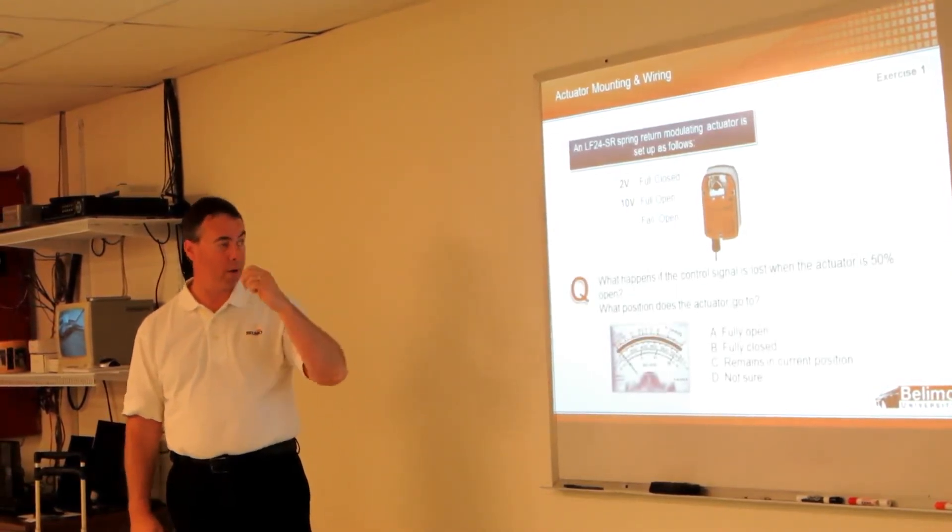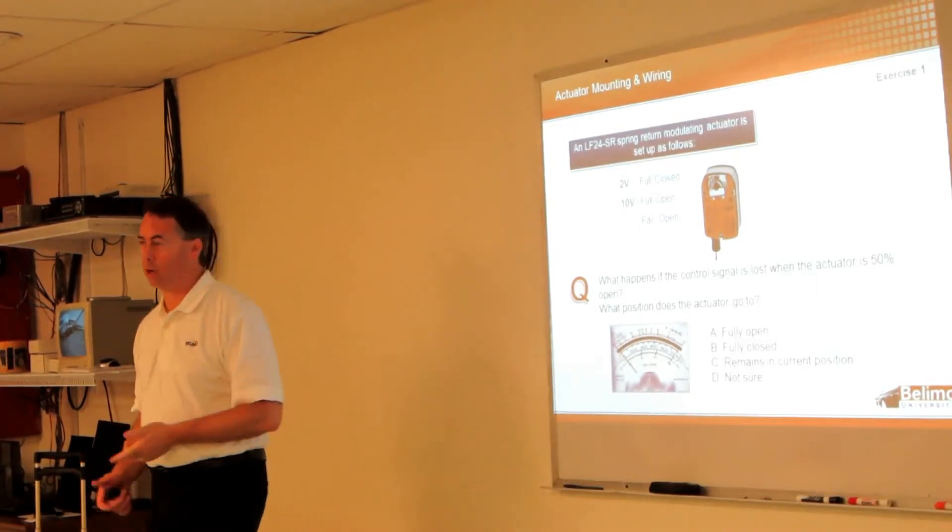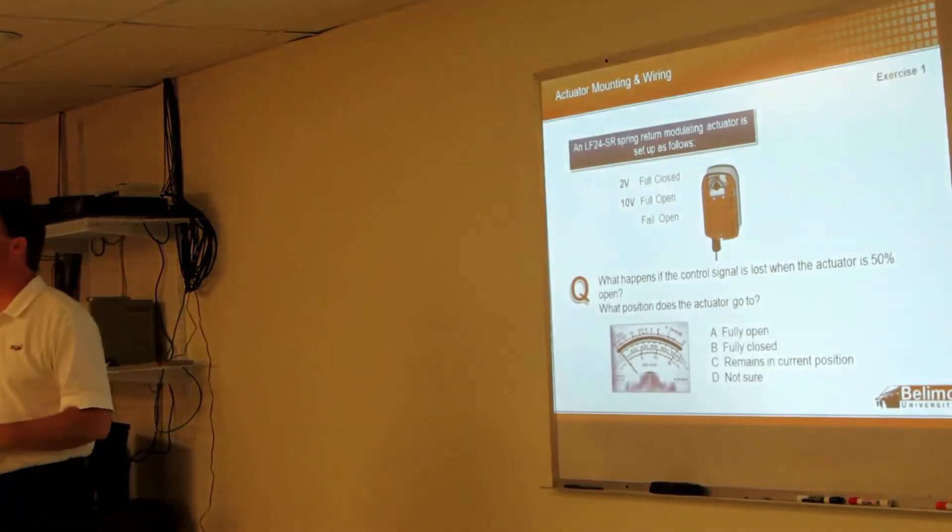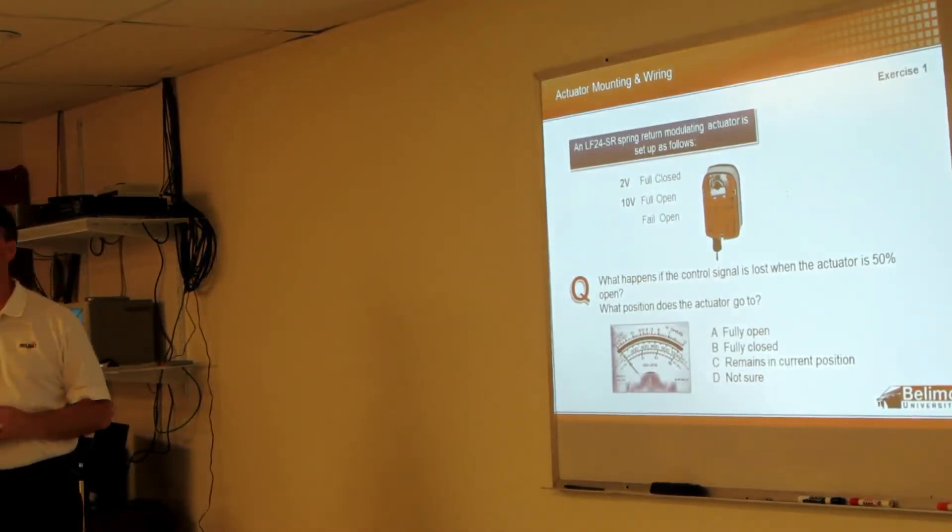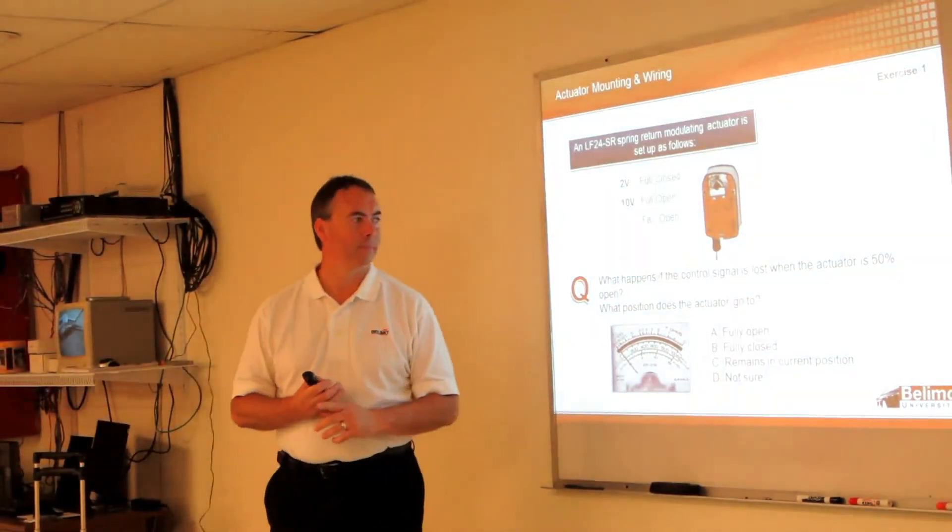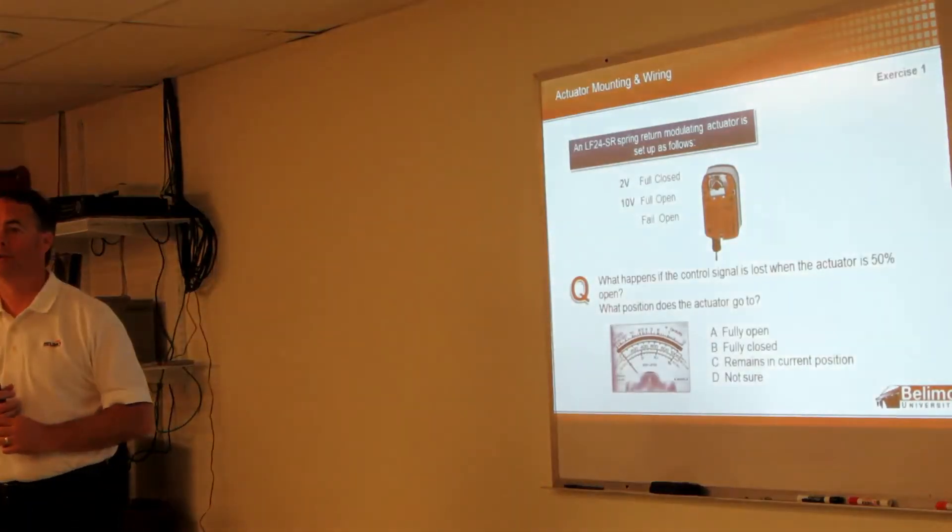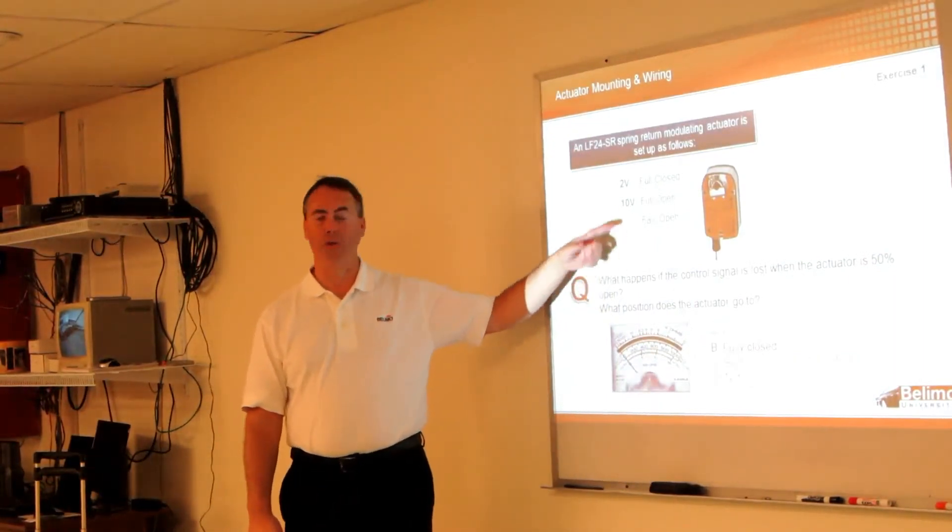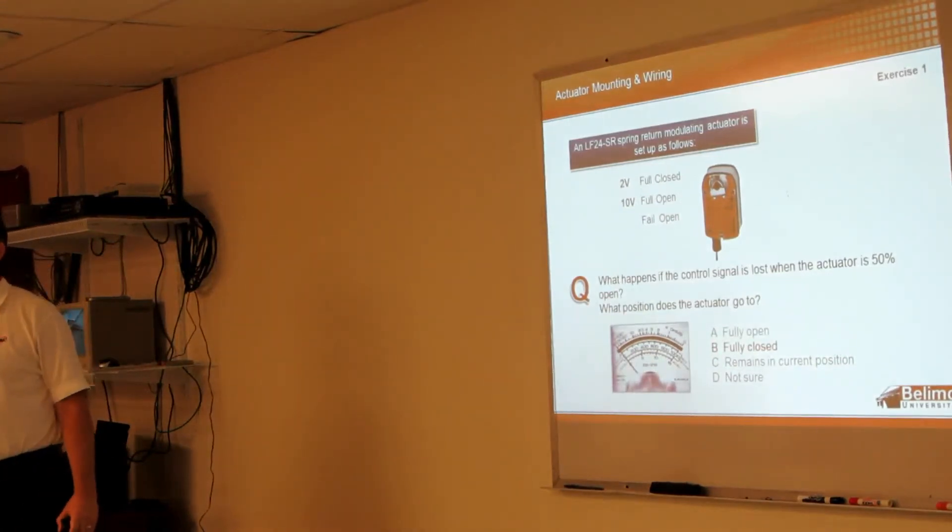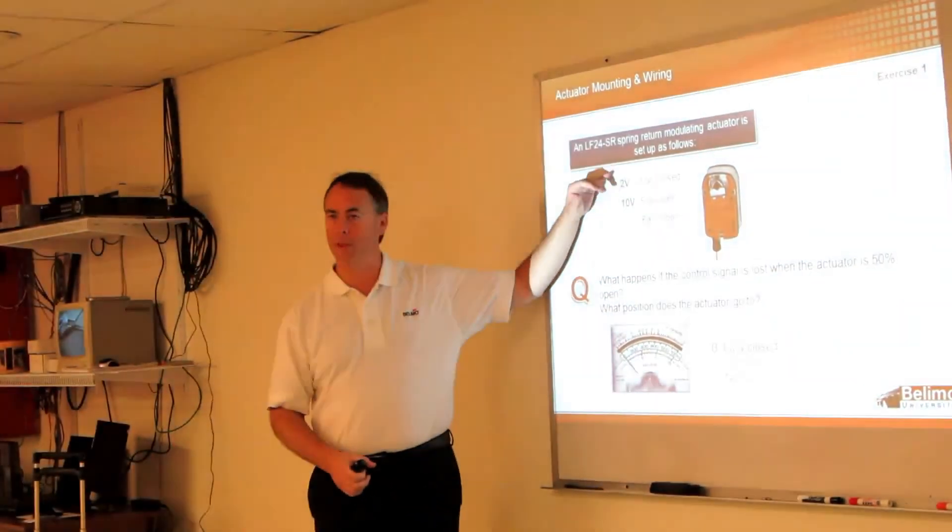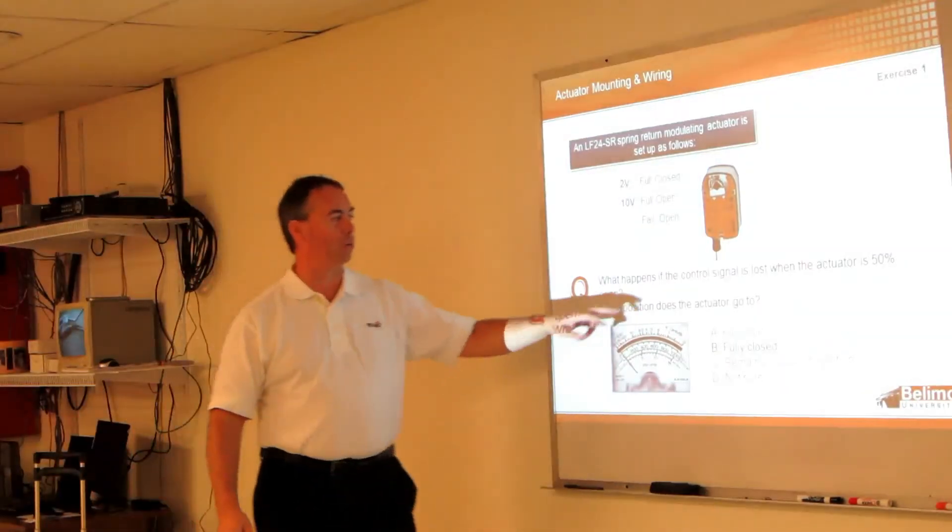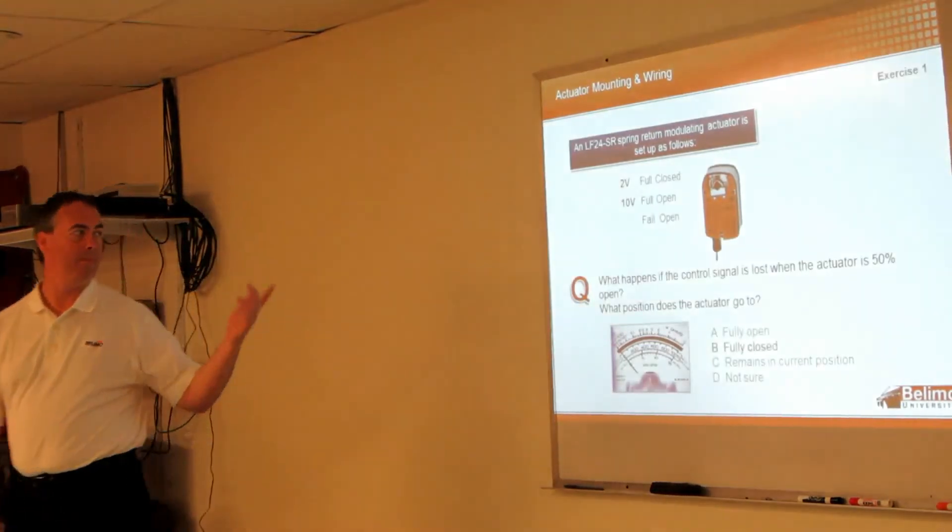So with this scenario, what is going to happen if we lose the control signal when it's at 50%? So 50% would be, we're at 6 volts. What's going to happen with the actuator? What position is it going to go? It's going to go closed. And I'll tell you why, because it's losing the control signal, so it's seeing 0 volts. So it's thinking that you've gone to the closed position, that you can give it a 0 or 2 volt signal. So it's going to close because we've lost the control signal. We didn't lose power. It still has power. So that's why it's going to go closed.